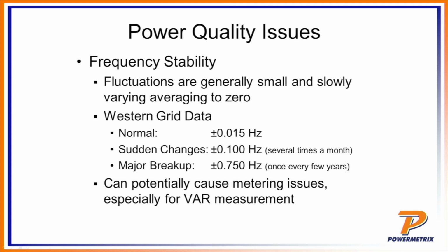If we look at a lot of the data here in the Western world, what we'll see is normal deviation should be no more than plus or minus 15 millihertz. That's 15 thousandths of a hertz. So once again, we have very good regulation on our frequency. A sudden change is defined as up to plus or minus 1/10 of a hertz. And that may occur several times a month, just depending on the situation. Once again, most utility equipment is designed, or most equipment in general is designed to accommodate that. It shouldn't be a problem.